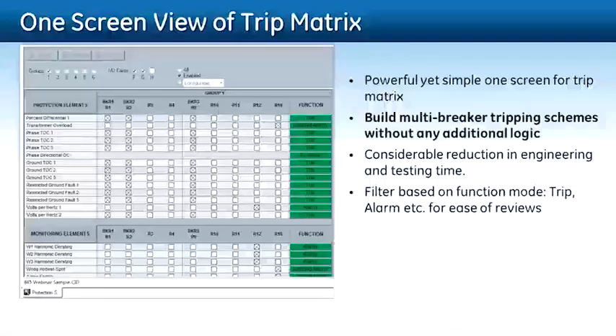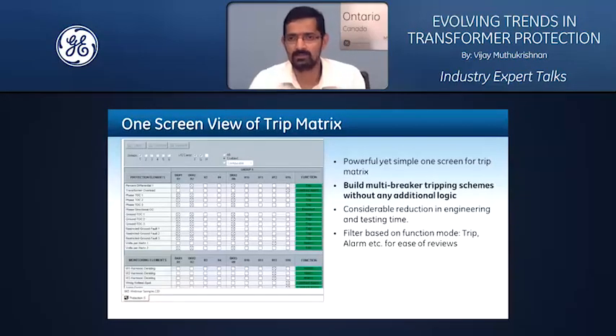The next one is another powerful feature in our Enervista setup program called Protection Summary. We have taken a lot of enhancements around this Protection Summary, especially in 845 and the overall 8 series platform. When you think about 845, assume a 3-winding application. That means you have 3 breakers connected to the transformer and the relay is seeing and controlling all 3 breakers. You are defining your protection elements such that certain elements you want to trip all 3 breakers, certain elements you want to just trip 1 breaker, in some other elements you want to trip 2 breakers, or some of them are alarm elements. In order to do this, traditionally you would end up building a logic in your relay and building that logic into an output relay driving.